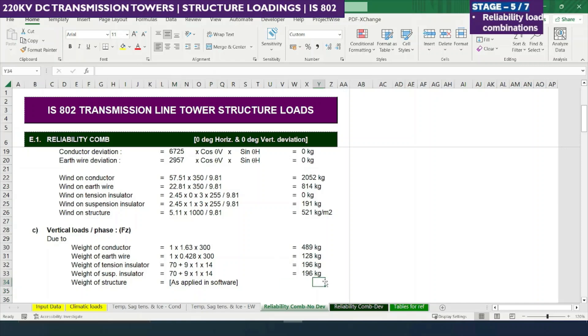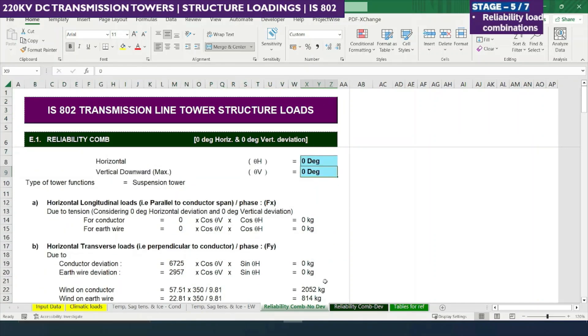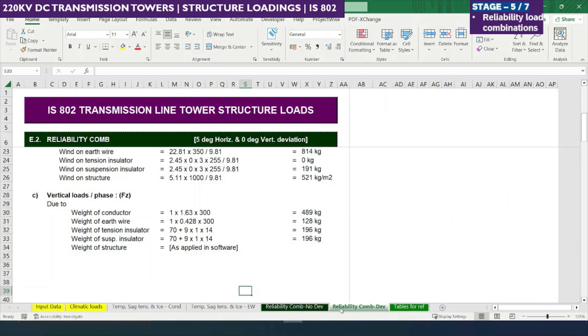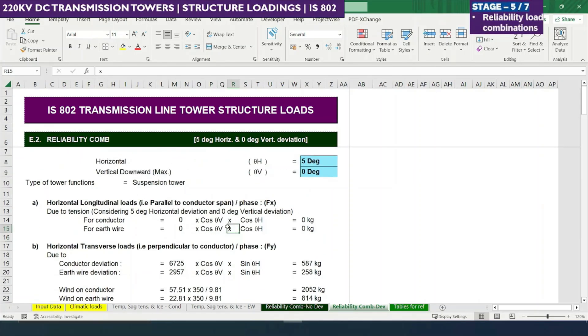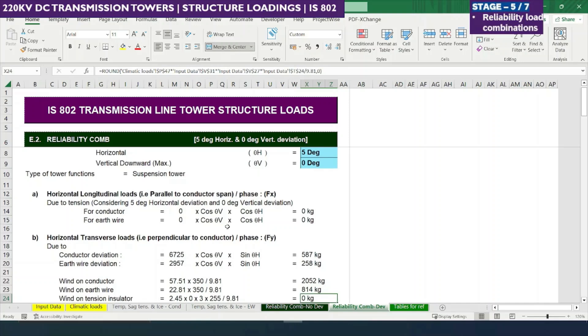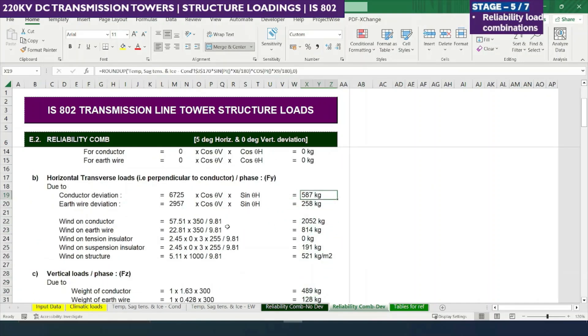This is the condition where there is no conductor or earth wire deviation. As we know, a suspension tower can have up to 5 degrees of conductor deviation. We can also calculate loads for a deviation case — for example up to 5 degrees. With zero vertical deviation, if deviation is zero there will be no transverse deviation loads. But considering maximum deviation of 5 degrees, the conductor deviation force is 587 kg and for earth wire it is 258 kg.